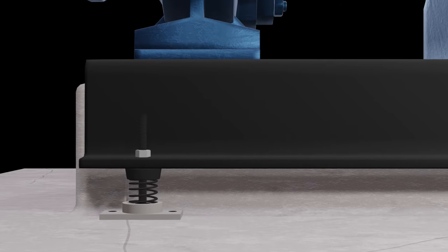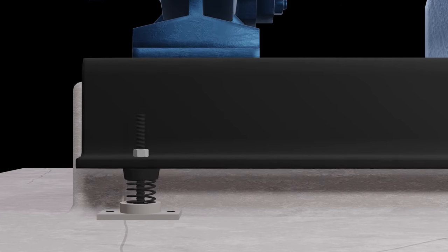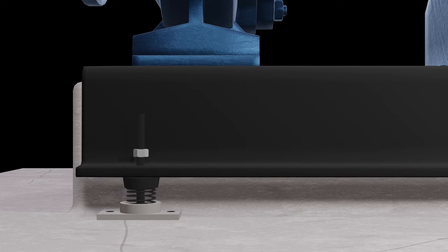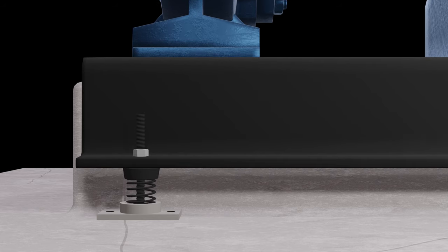If you do not know the proper compressed height, step on the machine to see how springy the isolators are. If they move easily, check with your supervisor or engineering department to confirm that they are adjusted correctly.